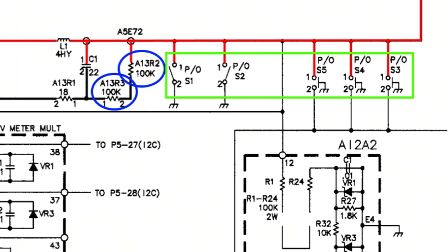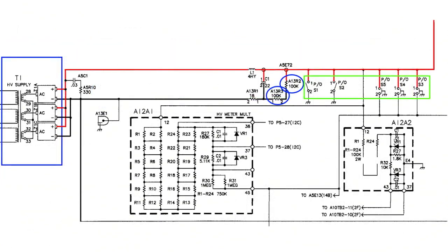And that's not a very pleasant thing to see if the transmitter is up and running and you yank a door open. That's going to make a heck of a flash. But they're there to protect you. Those things can get sticky and sometimes they don't work. They just don't close. They stay open. That's when that stick there comes in handy to short it out.